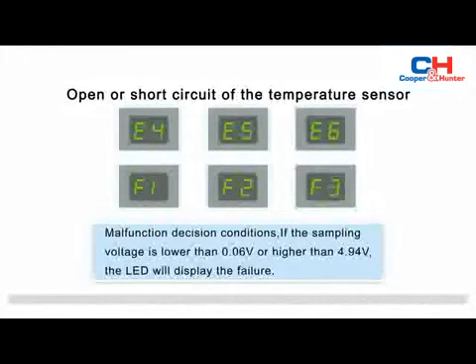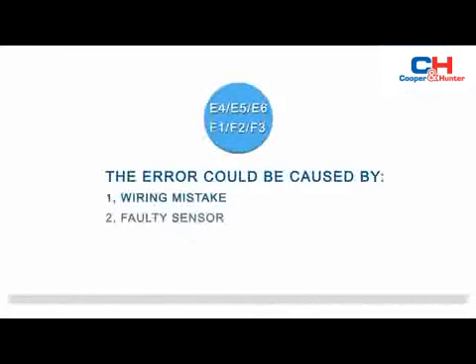Malfunction decision conditions: if the sampling voltage is lower than 0.06 volts or higher than 4.94 volts, the LED will display the failure. The error could be caused by: 1. Wiring mistake. 2. Faulty sensor. 3. Faulty PCB.